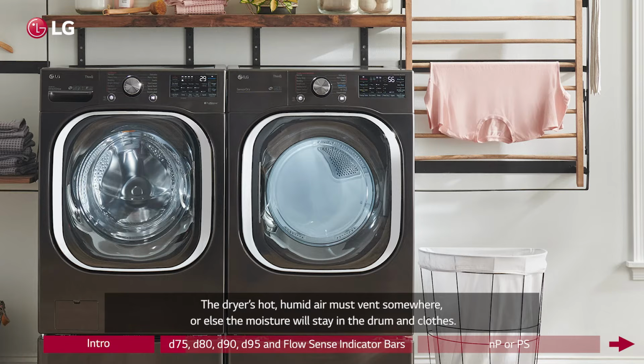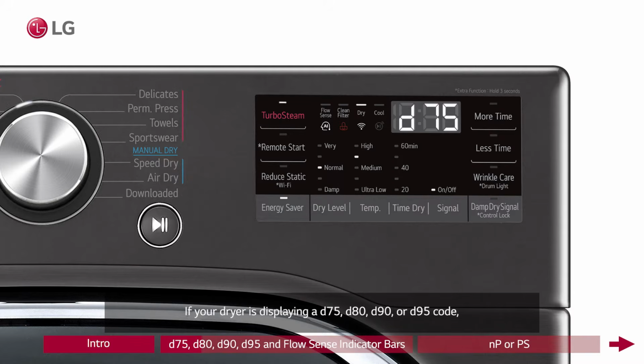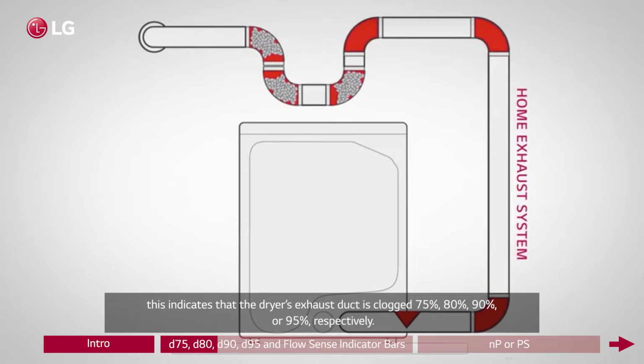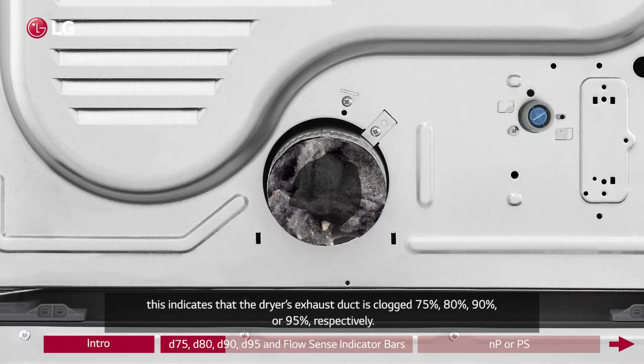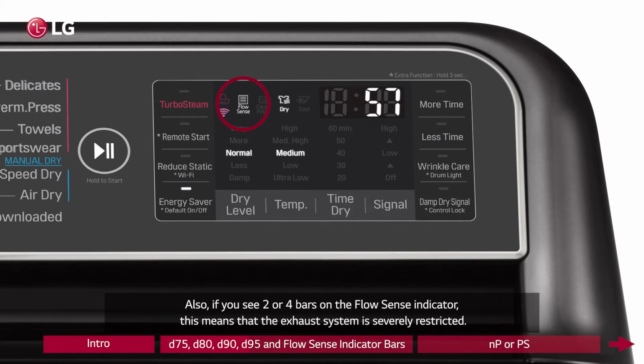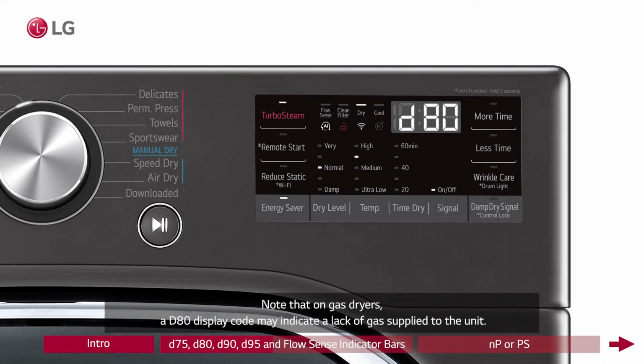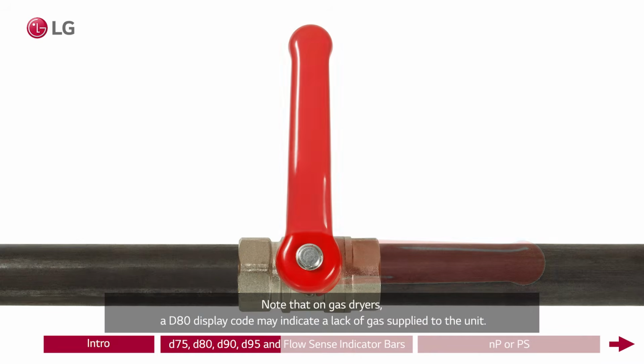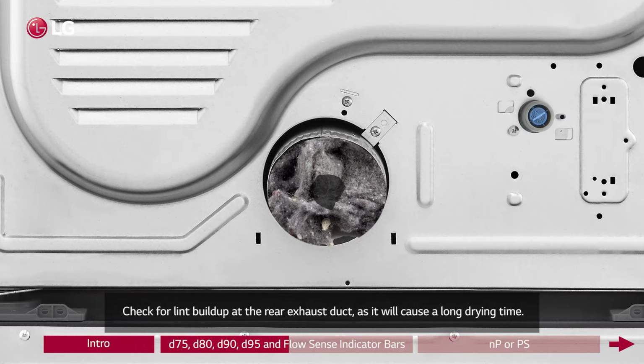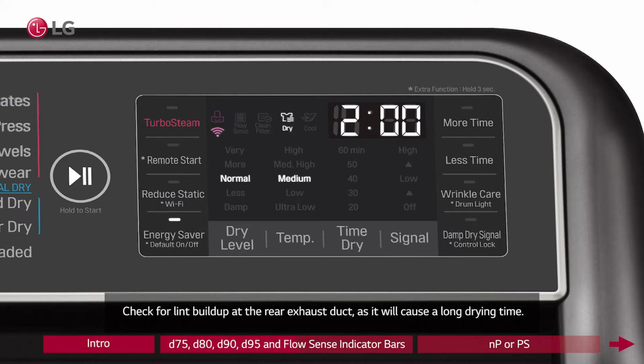The dryer's hot, humid air must vent somewhere, or else the moisture will stay in the drum and clothes. If your dryer is displaying a D75, D80, D90, or D95 code, this indicates that the dryer's exhaust duct is clogged 75%, 80%, 90%, or 95%, respectively. Also, if you see 2 or 4 bars on the flow sense indicator, this means that the exhaust system is severely restricted. Note that on gas dryers, a D80 display code may indicate a lack of gas supplied to the unit. Check for lint buildup at the rear exhaust duct, as it will cause a long drying time.